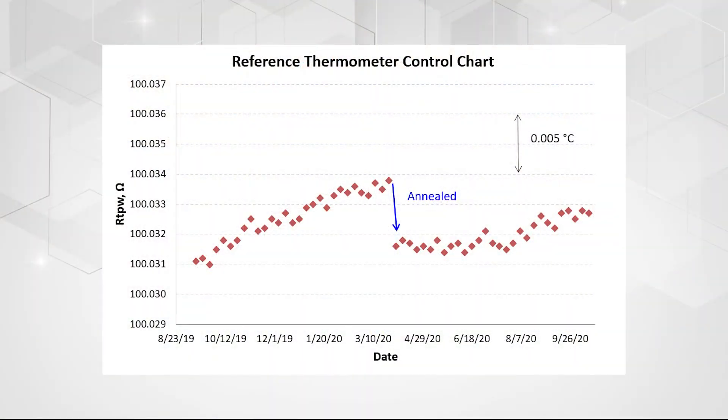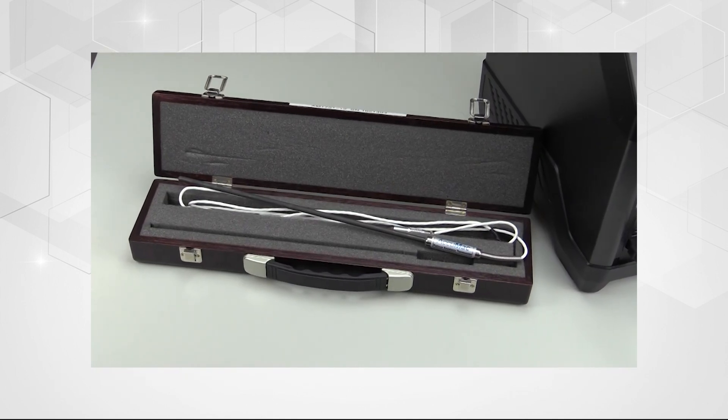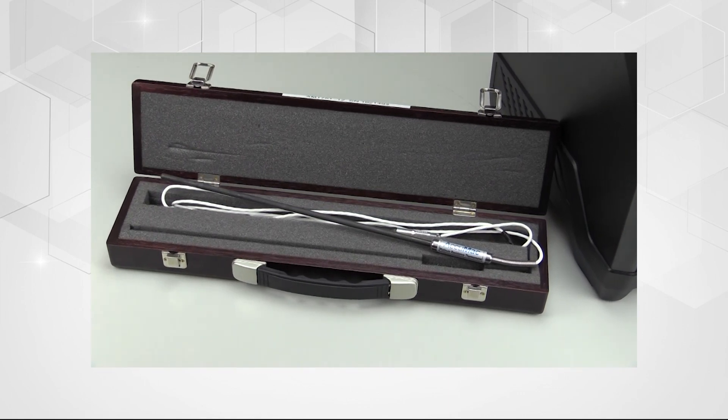Now that we have annealed the probes to relieve stress and reduce oxidation, we want to do our best to care for the internal platinum sensing elements by handling them carefully and storing them appropriately.